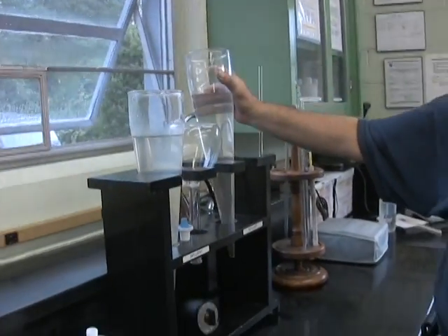With the temperature change, you start getting sloughing and stuff like that off the filter, and you'll have a little bit more debris in there. But normally this is pretty clear, and that's really coming out of the secondary clarifier we're taking a sample from, because we don't have an effluent unless we're discharging to the river. But that kind of tells us that our process is working in the plant. Temperature changes have big impacts on the filters, as far as some of the bacteria sloughing off and changing over. So at this time of the year, that's what we usually get. We'll get a lot of solids coming out, and it'll clear itself up when we get into a little bit colder weather. All right.